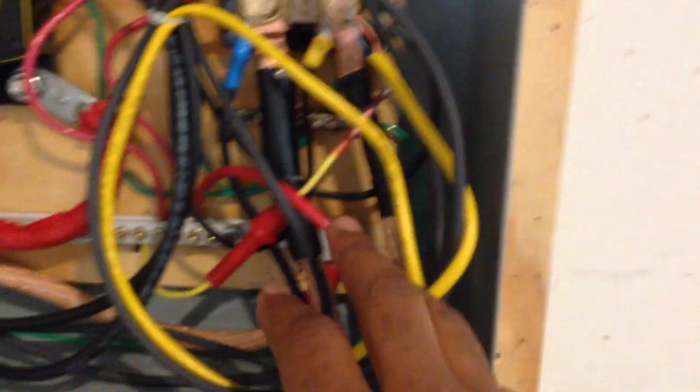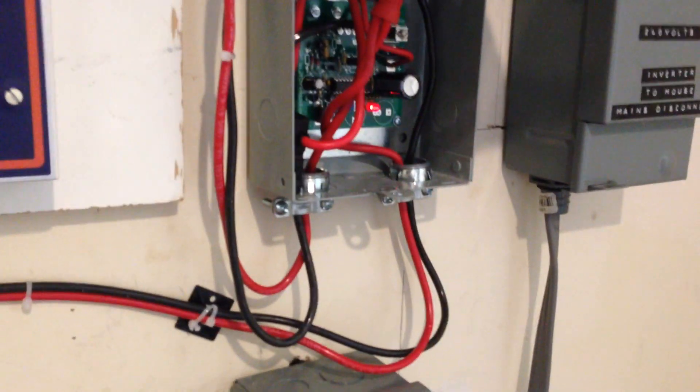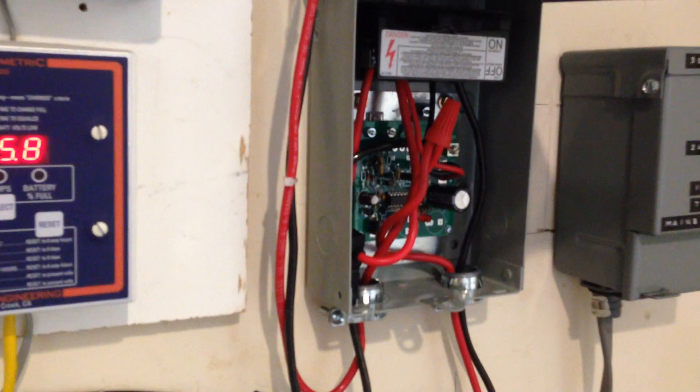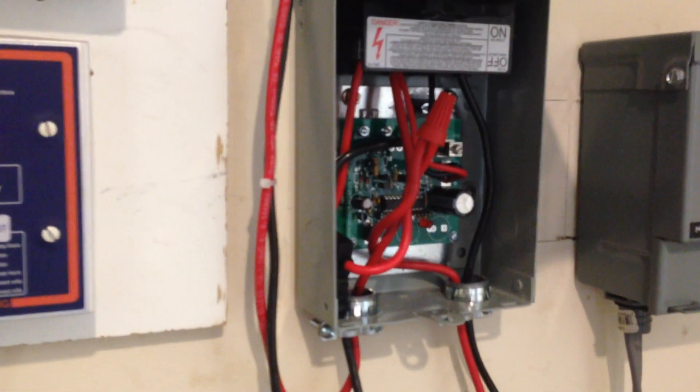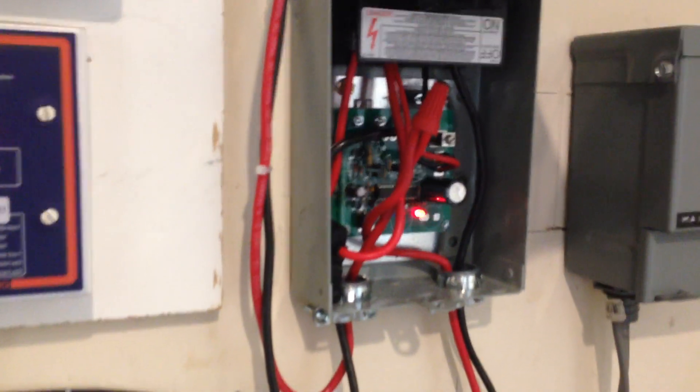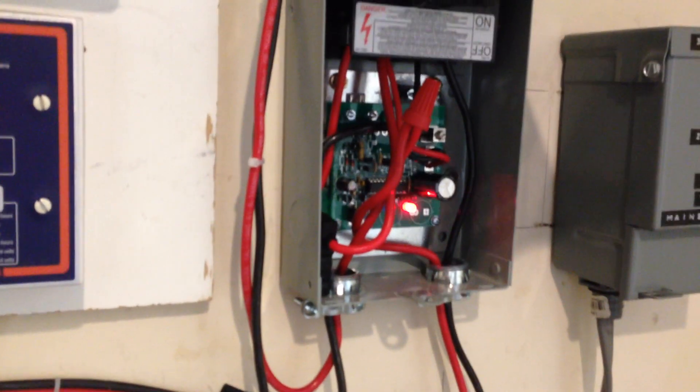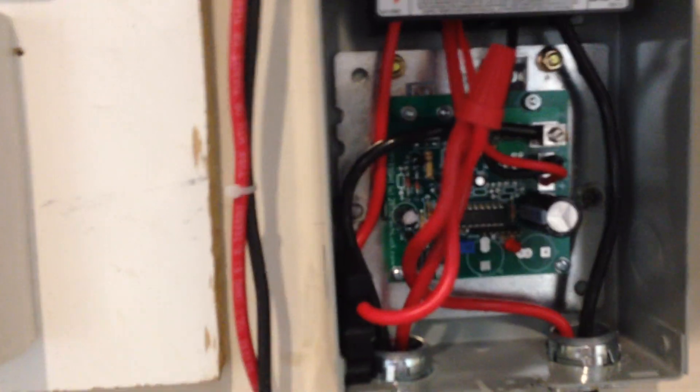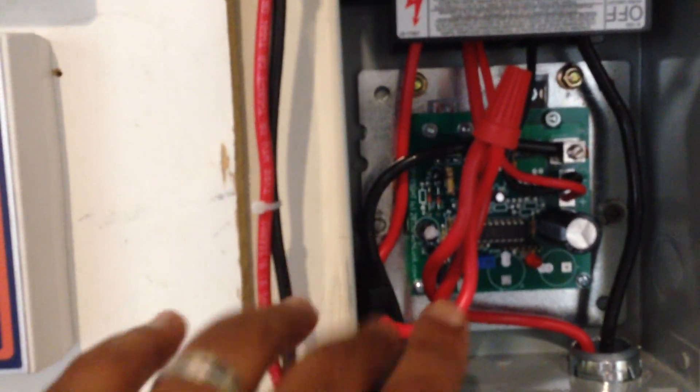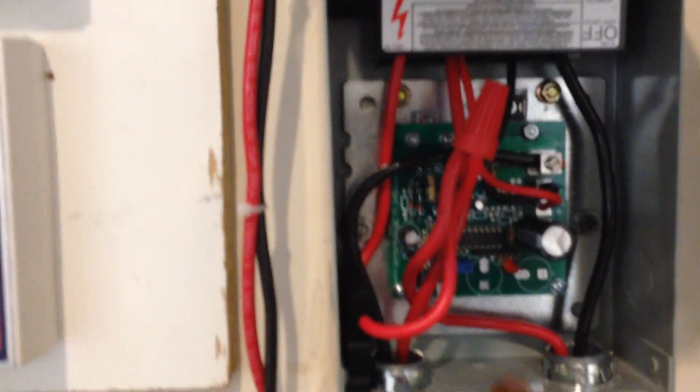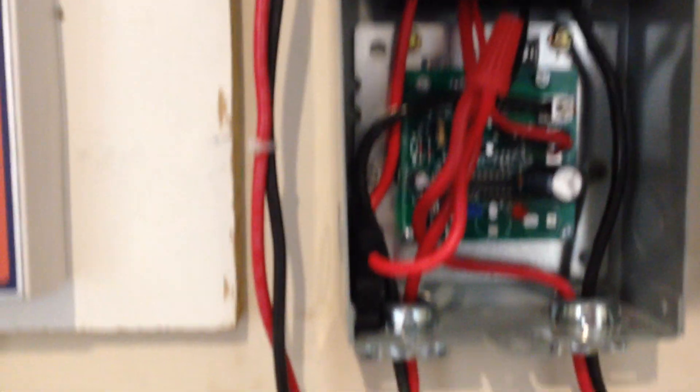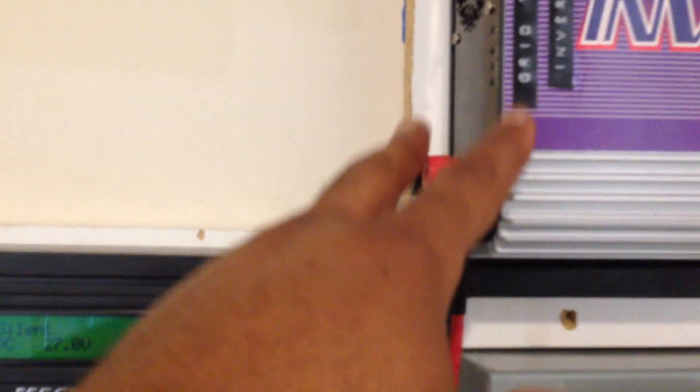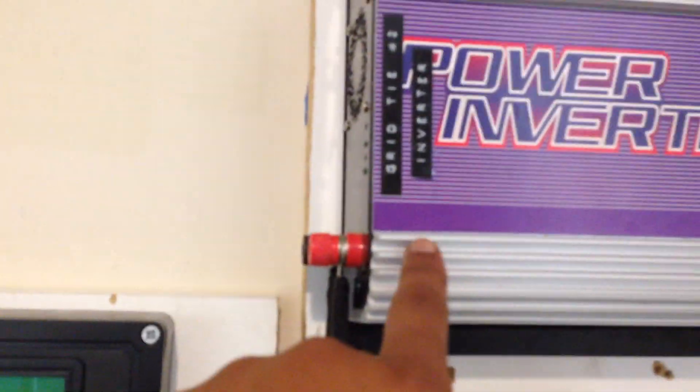Now, these cables here are 8 gauge, they're not 10 gauge. So I followed the recommendation, so I went with an 8 gauge wire, and the length is within 5 feet. Actually, it's about maybe 3 and a half, 4 feet, to the GTI controller, so that I will have minimum voltage loss. From here, it goes out into the GTI, and I hooked everything in there. So these are 8 gauge cables that I actually provided from inside to the GTI, and also following up to the grid tie inverter, they're 8 gauge.